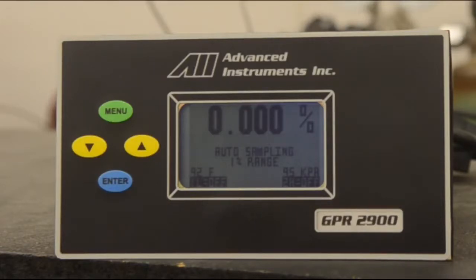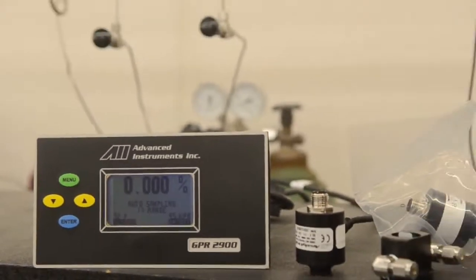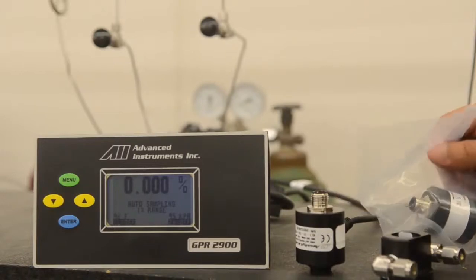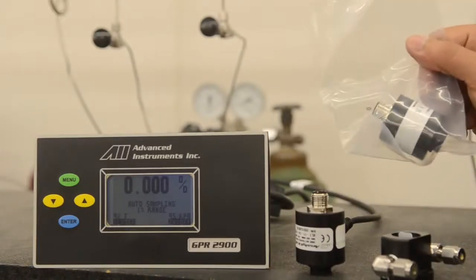Now, if you notice, you're on auto sampling at the 1% range. For default, the analyzer will be auto sampling, and you can change that later, but for now this is acceptable for air calibration. You can also notice that you'll see the temperature, pressure, and alarm values. We'll go over how to change the alarm values later on in this video, but for now we will do a new sensor install.